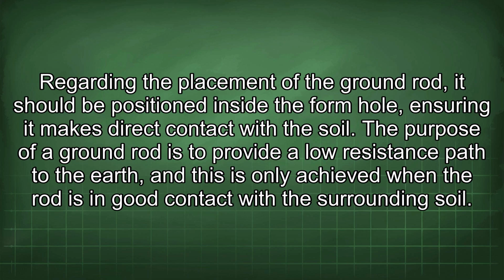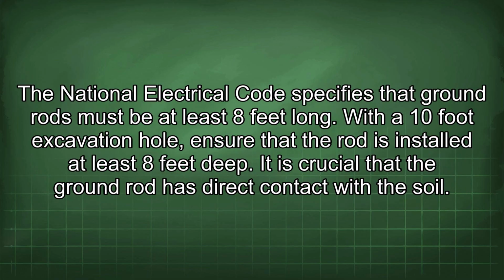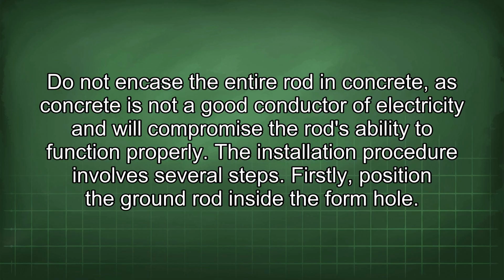The purpose of a ground rod is to provide a low resistance path to the earth, and this is only achieved when the rod is in good contact with the surrounding soil. The National Electrical Code specifies that ground rods must be at least 8 feet long. With a 10-foot excavation hole, ensure that the rod is installed at least 8 feet deep. It is crucial that the ground rod has direct contact with the soil. Do not encase the entire rod in concrete, as concrete is not a good conductor of electricity and will compromise the rod's ability to function properly.